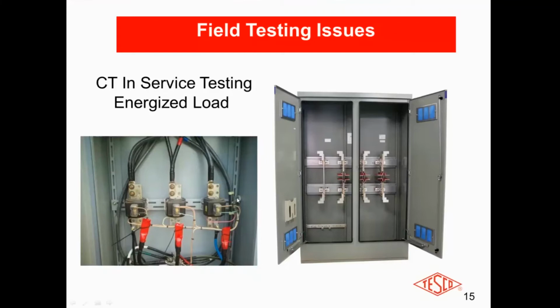We're measuring CTs because essentially the meter on your installation or service is going to receive all its current from this point - it's a transformer rated customer. So the incoming current going through the CTs, in this case phase A, is also going to output from the secondary, which then goes all the way through into the meter itself.